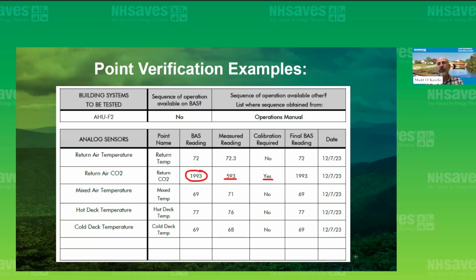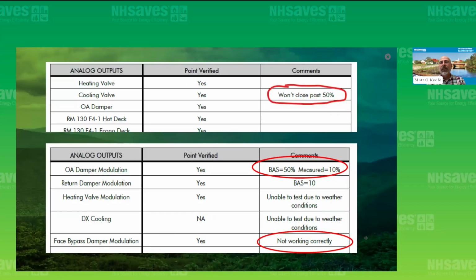So one bad $50 return duct sensor can lead to thousands of dollars of wasted energy when it's just not reading right. In this case, this example shows the CO2 sensor reading very high compared to what was actually found in the field. This one found valves that work up to a point, but they won't close entirely. And then we're also finding conditions that don't line up with the building management system. So all of these are leading to wasted energy, and again, good opportunities to work with a customer to fix those, increase comfort, save energy, all good stuff.